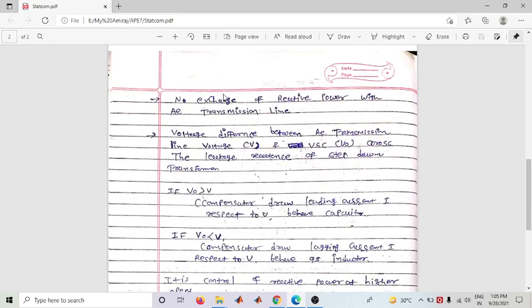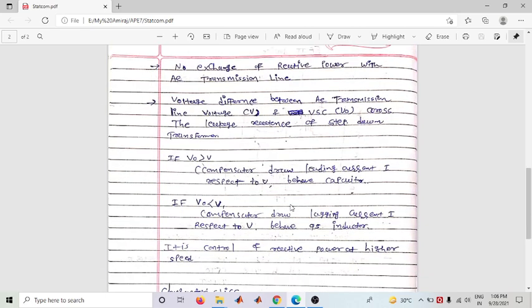There are two conditions. First, when V0 is greater than V — meaning the voltage source converter voltage is higher than the transmission line voltage — the compensator draws a leading current. It behaves like a capacitor, supplying leading current to maintain the voltage.